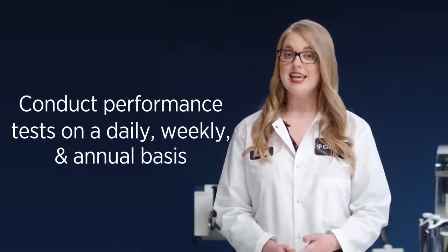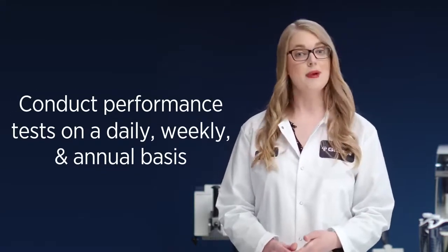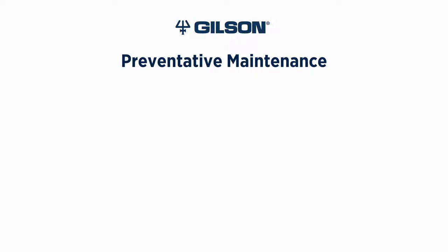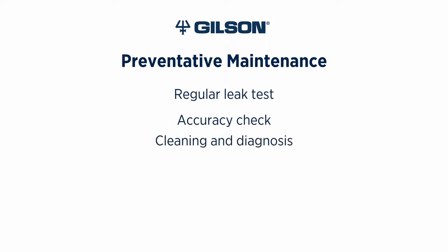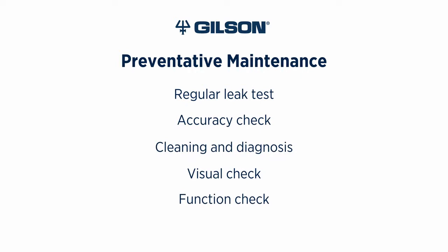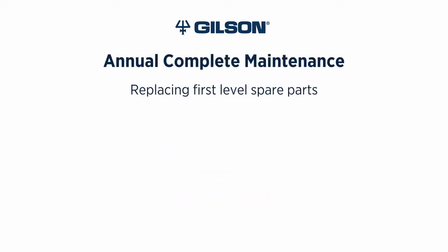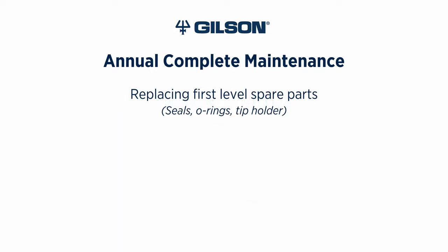In order to keep your pipettes in peak working condition, you should conduct performance tests on a daily, weekly, and annual basis. Preventative maintenance consists of a regular leak test, and on a weekly to quarterly interval, you should conduct an accuracy check, cleaning and diagnosis, visual check, and function check. Complete maintenance should be done annually and involves replacing spare parts of the first level, such as seals, O-rings, the tip holder, etc., and adjustment calibration.